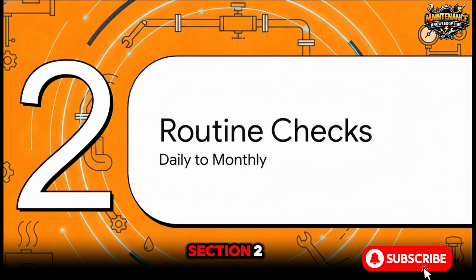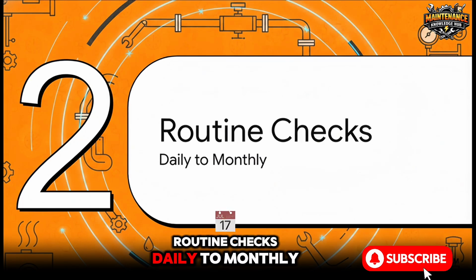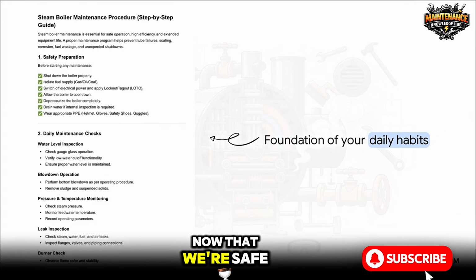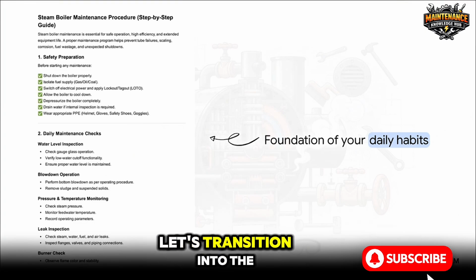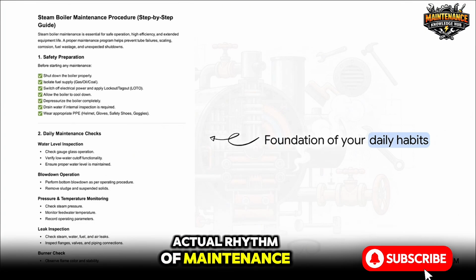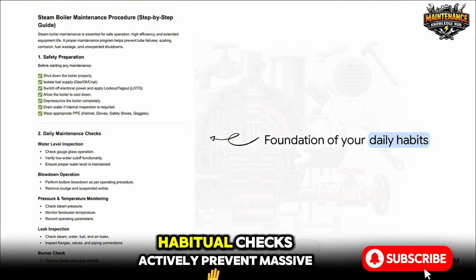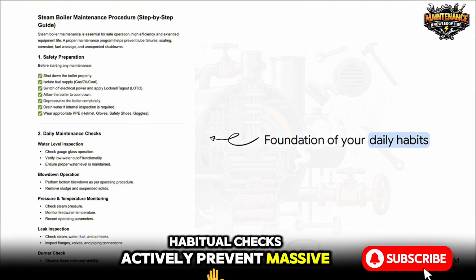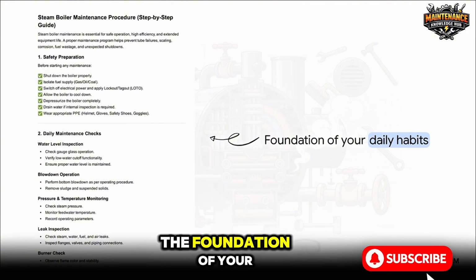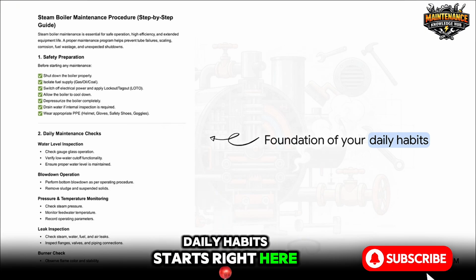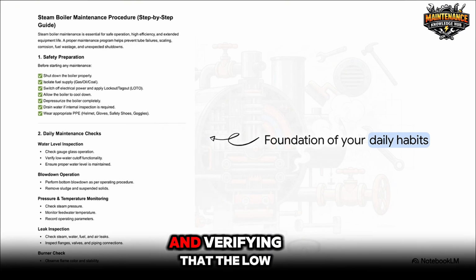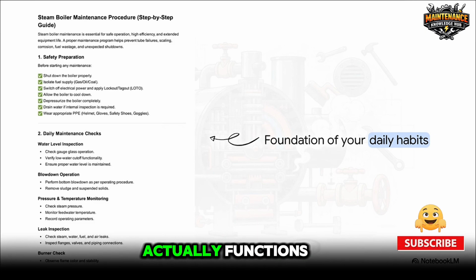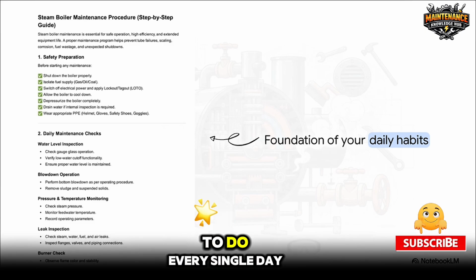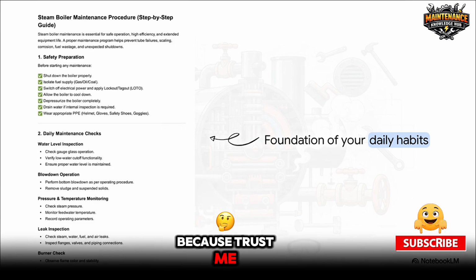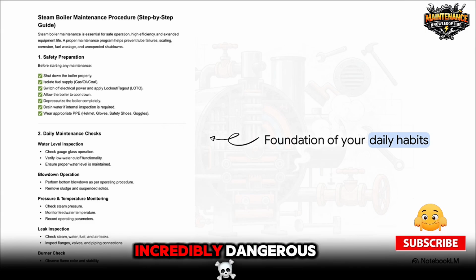Moving right along to Section 2, Routine Checks Daily to Monthly. Now that we're safe and secured, let's transition into the actual rhythm of maintenance. It's fascinating how small, habitual checks actively prevent massive, costly catastrophes. The foundation of your daily habits starts right here. Checking the gauge glass operation and verifying that the low water cutoff actually functions are things you have to do every single day. Because trust me, a low water scenario is incredibly dangerous.